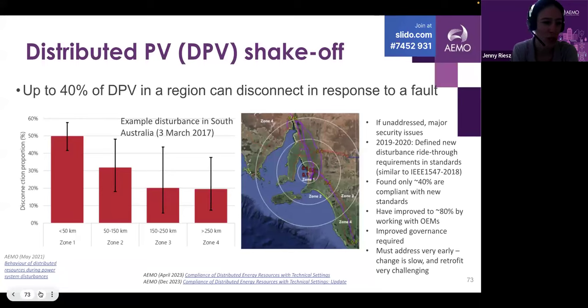In response to that, we saw a very large proportion of the distributed PV trip off. Within a 50-kilometre radius, it was about half of the PV that tripped, and extending right out to about 250 kilometres away, which covers a lot of the state.